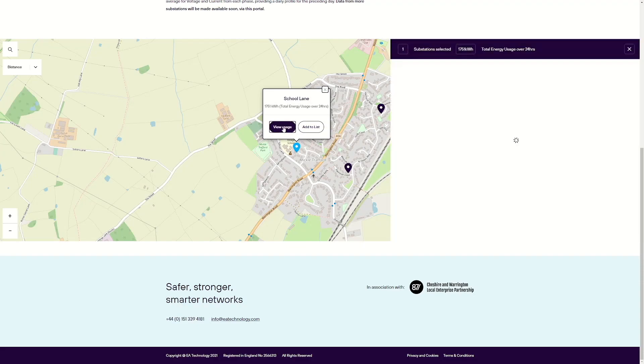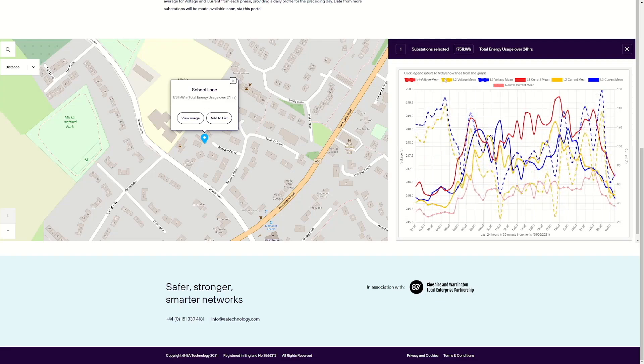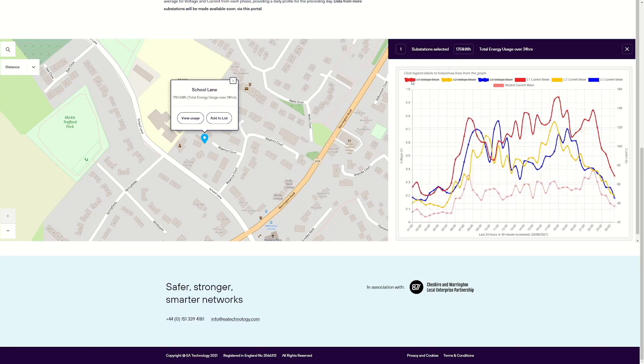Selecting the View Usage option will give us more information. By default, the graph is showing average current and voltage for each phase for each half-hourly period of the last full day. At the time this video is recorded on Wednesday June 30th, you can see that data reflects Tuesday June 29th. It is possible to disable or reactivate individual traces at the top of this graph. Disabling the voltage values clears up the graph, and we can now see a typical domestic network load profile across all three phases. We will be updating this functionality in the future to provide information on the energy utilized by the substation over the same period, and how this relates to the capacity of the assets, so please keep checking back.